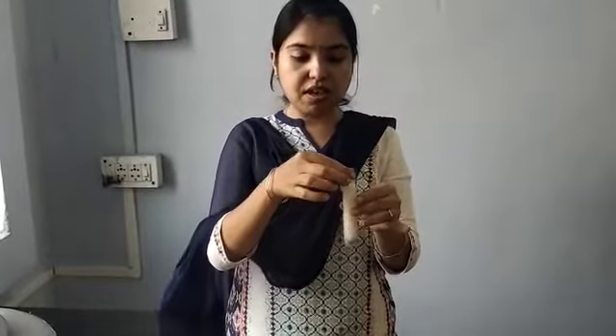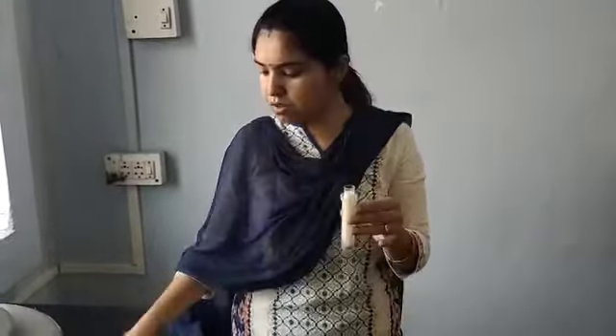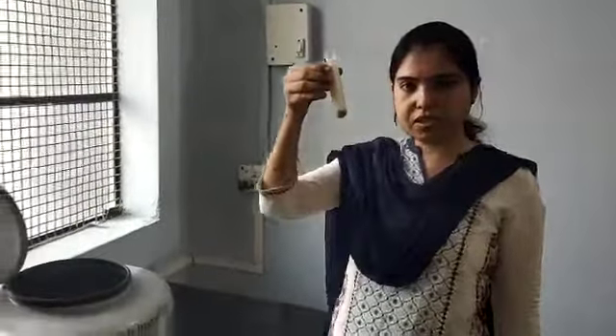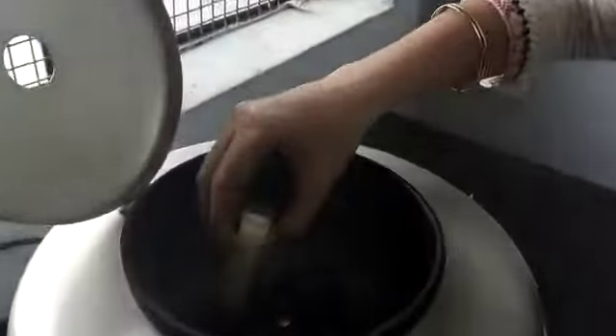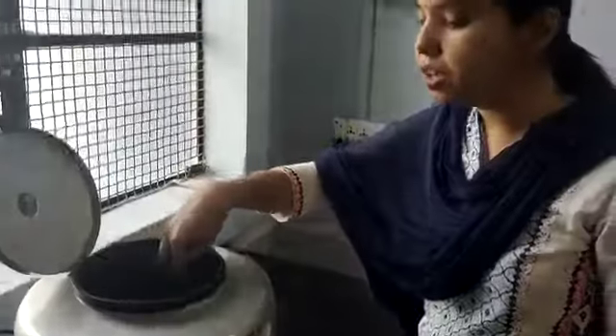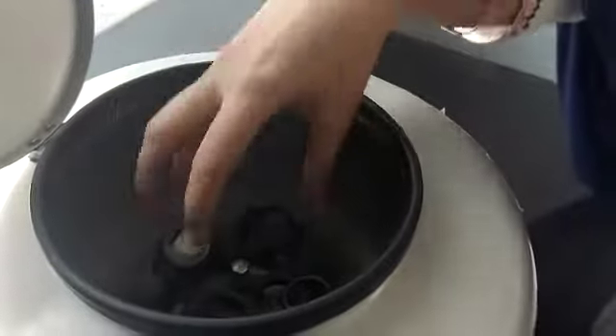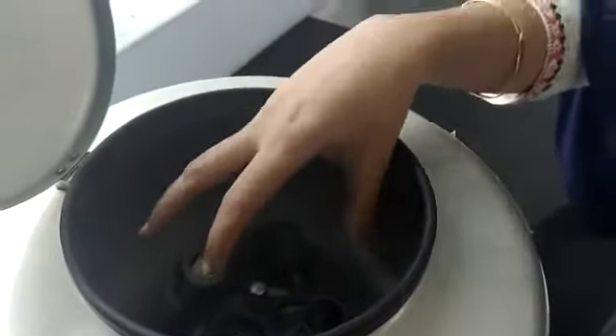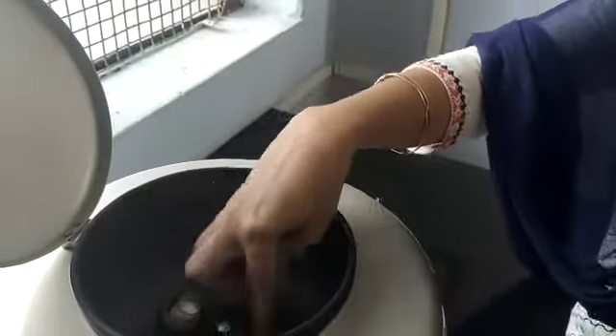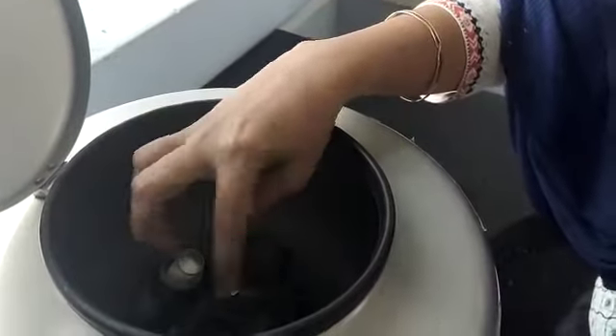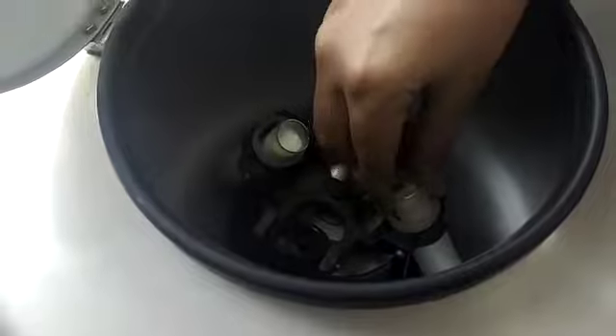So you can see that this moves around this bucket, so it may fall off. So there is a rubber insert that is provided with this. You have to insert it here so that it will hold the centrifuge tube during the rotations. So I am loading this filled centrifuge tube into the hole of the rotor. Always we need to balance the weight here, otherwise there may be breakage of the centrifuge tube. We need to balance the weight, it should be symmetrically balanced. So you have to load all the centrifuge buckets, or you can also insert another bucket towards the opposite axis. So this will balance the weight and this will not damage the instrument during the operation.